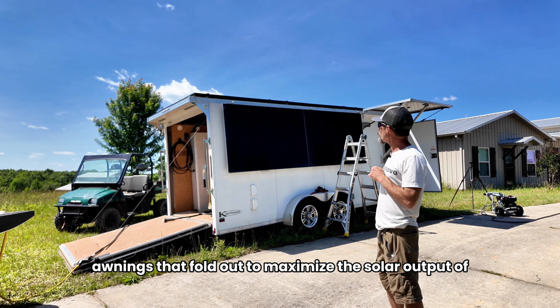Why would you want to run the generator when the grid is up? There are two good reasons. First, you might choose a power solution like the NERD to feed a facility that needs to stretch a very small grid connection a lot further. If your grid connection is totally tapped and you don't have available battery reserve or solar present, you could turn that generator on to supplement and power more things on site.